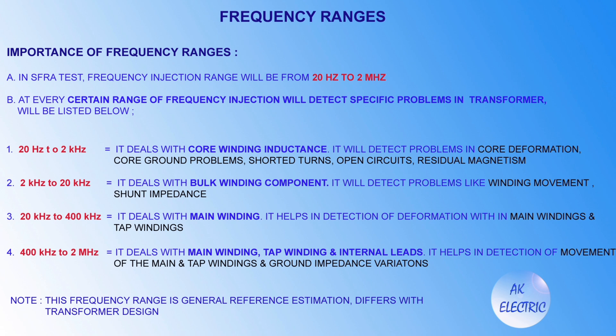Regarding frequency ranges in SFRA test — frequency injection is from 20 Hz to 2 MHz, and each range detects specific problems. 20 Hz to 2 kHz deals with core winding inductance and detects core deformation, core ground problems, shorted turns, open circuits, and residual magnetism. 2 kHz to 20 kHz deals with bulk winding components and detects winding movement and shunt impedance. 20 kHz to 400 kHz deals with the main winding and detects deformation within main and tap windings. 400 kHz to 2 MHz deals with main winding, tap winding, and internal leads, and detects movement of main and tap windings and ground impedance variations. Note: these frequency ranges are general reference estimations only and differ with transformer design.